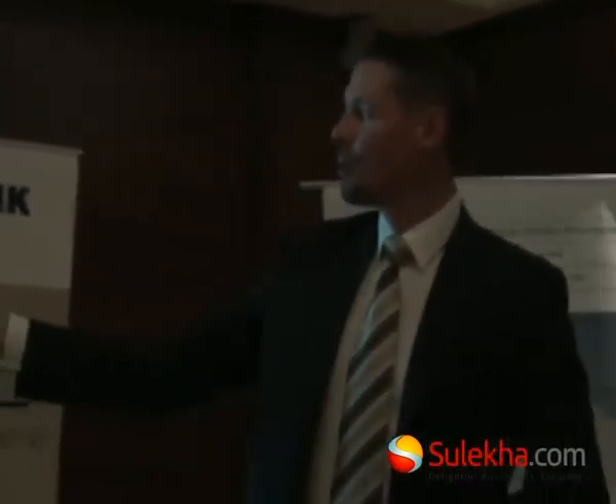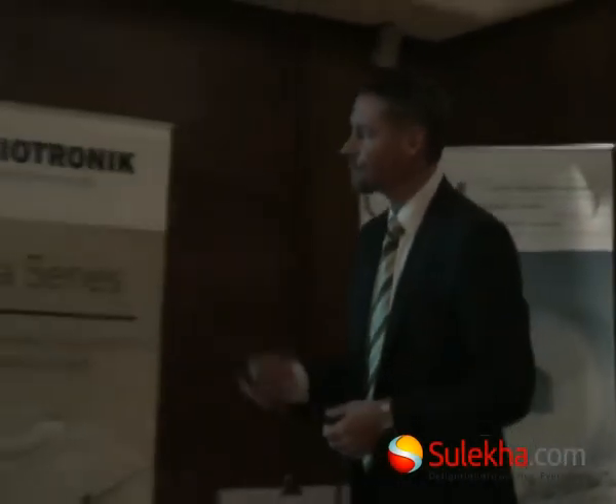So that's number 1. Number 2, which constitutes a much bigger problem for all cardiac implant devices, is the heat development in the wire, in the electrode. We have to imagine that an MRI acts like a microwave. So the leads will heat and discharge the heat in the heart. We cannot allow for that. That's why we have certain conditions, and with the ICDs we don't allow scanning of the chest zone. So a cardiac MRI is not possible, but that zone shrinks with the patient size.